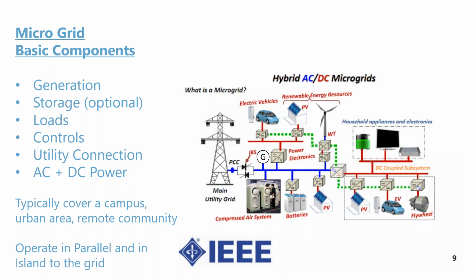Controls is the fourth component and is a device that provides communication between distributed energy sources, grid, photovoltaic, wind, storage, and loads, to maintain acceptable levels of frequency and voltage. And the last one is the grid. The grid gets connected to intelligent breakers that can disconnect or connect the grid back to the source.